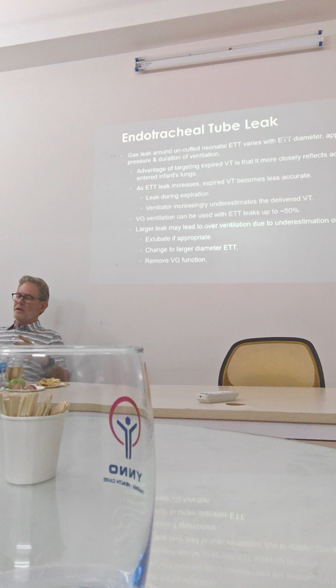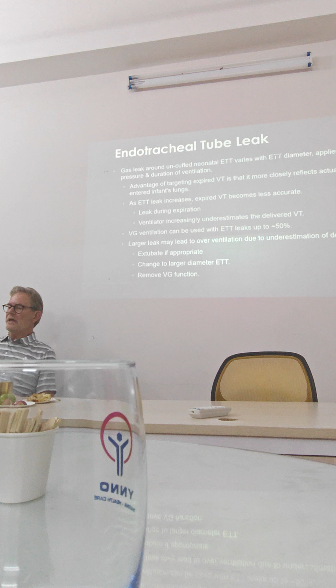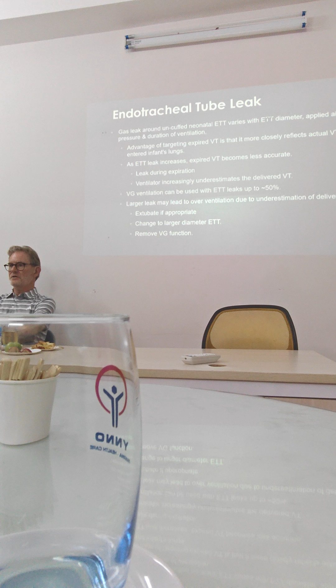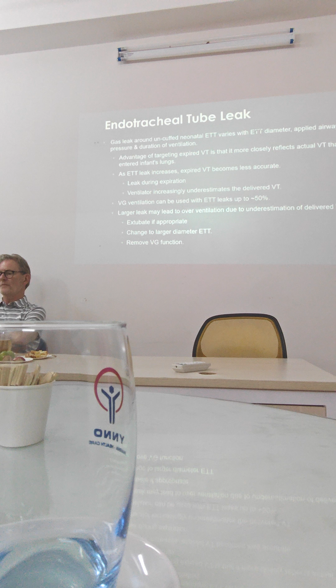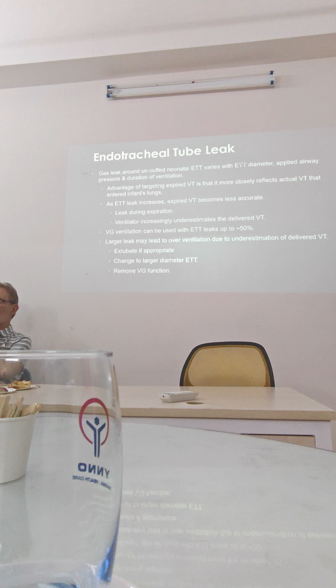Expiratory volume, because essentially expiratory volume tells you what went into the lung. The problem with ET leak is if you've got a large leak, you can also get leak during expiration, and so your measured tidal volumes start to become inaccurate. And most ventilators can cope with a leak up to about 50%, but once the leak gets beyond 50%, you really have no idea what tidal volumes are being delivered.